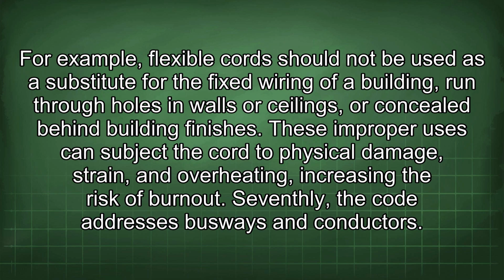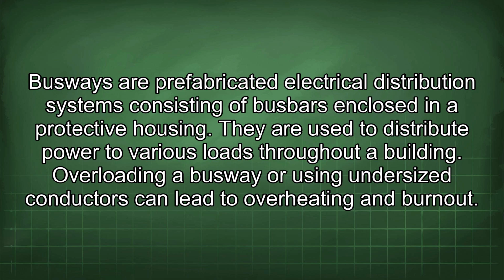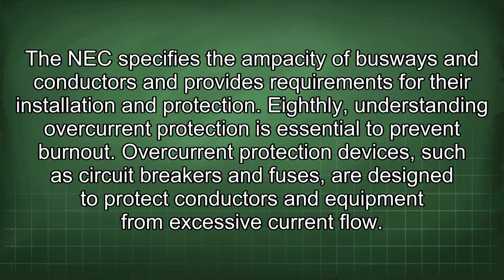Seventhly, the code addresses busways and conductors. Busways are prefabricated electrical distribution systems consisting of bus enclosed in a protective housing. They are used to distribute power to various loads throughout a building. Overloading a busway or using undersized conductors can lead to overheating and burnout. The NEC specifies the ampacity of busways and conductors and provides requirements for their installation and protection.